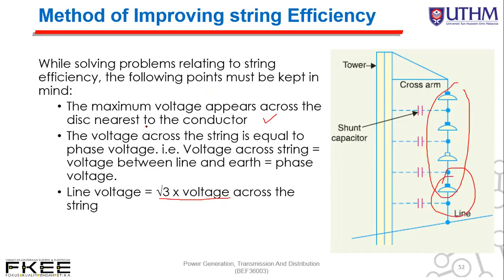When solving problems relating to string efficiency, keep in mind: maximum voltage appears across the disc nearest to the conductor; the voltage across the string is equal to the phase voltage. Do not use line voltage — use phase voltage as the voltage across the string.